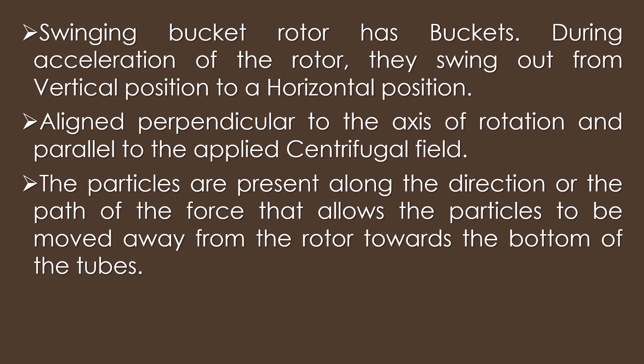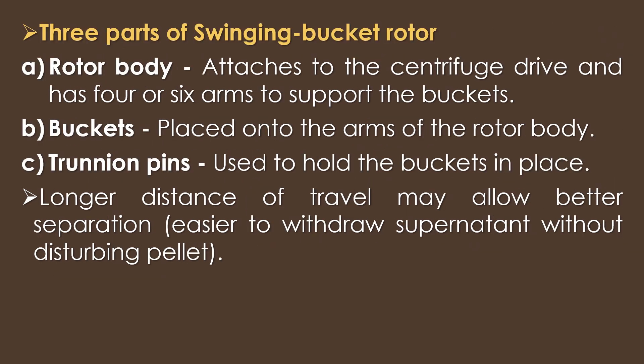In swinging bucket rotors, the particles are present along the direction of the force, which allows the particles to be moved away from the rotor towards the bottom of the tubes. A swinging bucket rotor system consists of three parts: the rotor body, buckets, and trunnion pins. The rotor body attaches to the centrifuge drive and has four or six arms to support the buckets. The buckets are placed onto the arms of the rotor body, and trunnion pins are used to hold the bucket in place. Long distances of travel may allow better separation, making it easy to withdraw supernatant without disturbing the pellet.